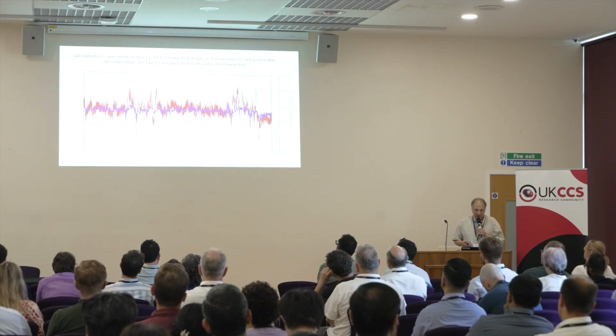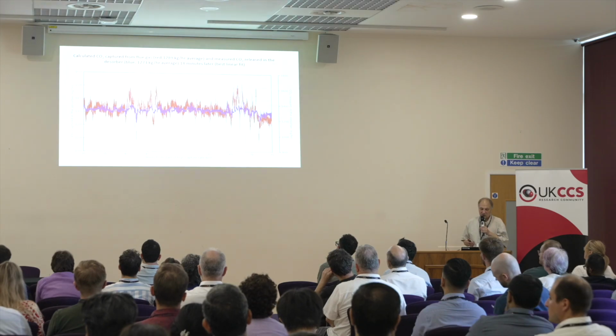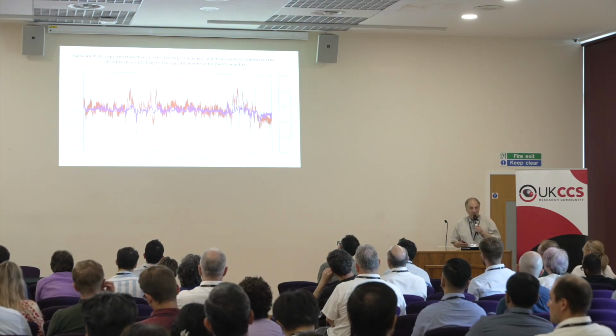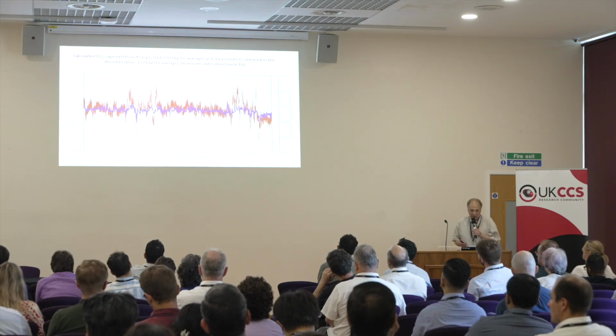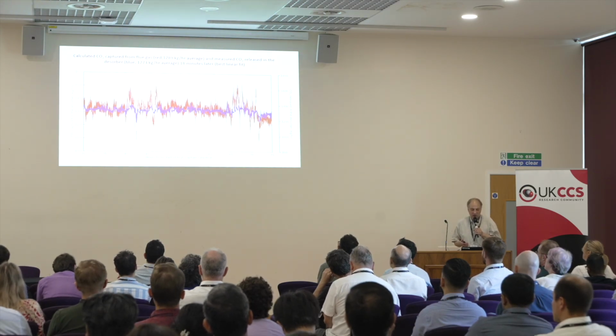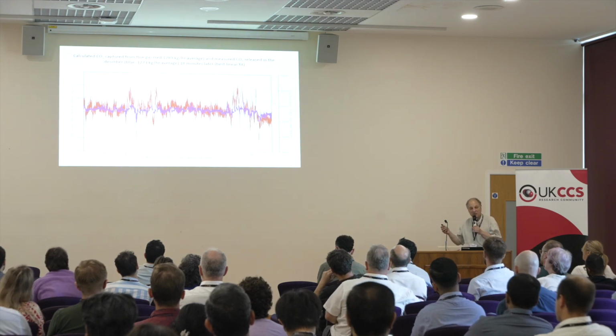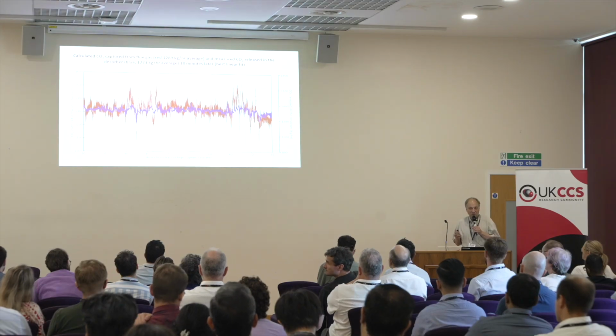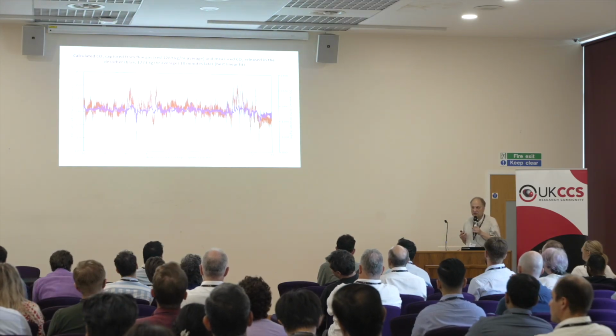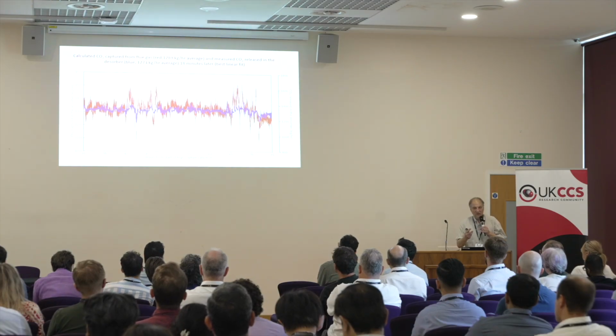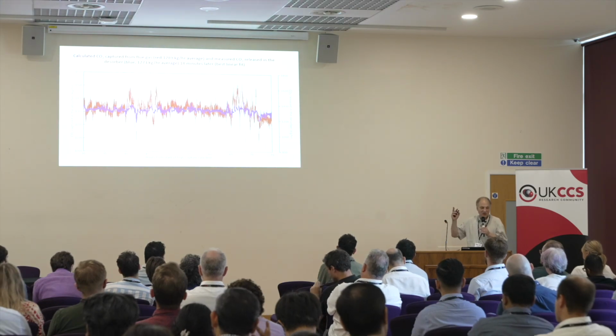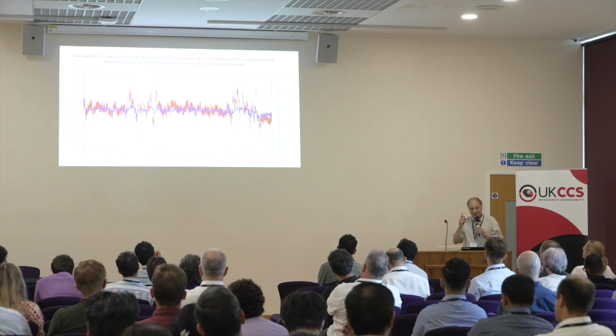And I'll give you one possible solution. Now the red is in fact the captured CO2, based on the gas concentrations and the flow rates. And then the blue is the captured CO2 again, but what's come out from the desorber. So the red is what we're capturing from the flue gas, and the blue is after it's been picked up by the solvent, gone all the way through the system, got cooked out, and has got to the CO2 delivery point. The other one took 20 minutes. This only takes 18 minutes. Who would have thought that would have been quicker?